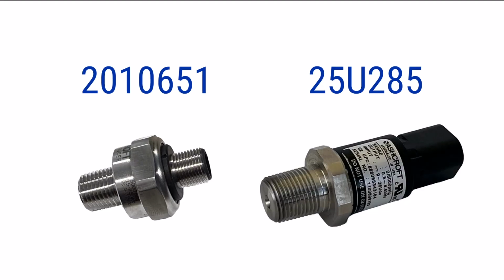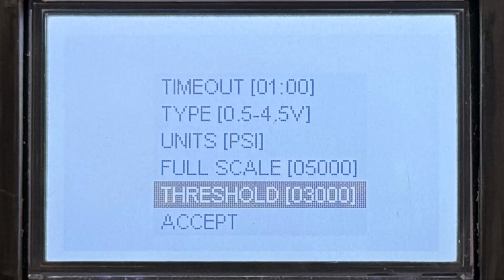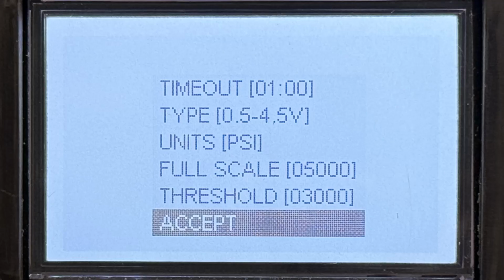If you are using one of the transducers that Graco sells, either part number 2010651 or 25U285, then the default settings for the G3 Max are correct, and you only need to decide where to set the threshold. If 3000 psi is more than you need for your system, you can set it to a lower value, or if you need more than 3000 psi, you can set it to a higher value. Be sure to move the cursor down to accept and then press the right arrow key to save the change.